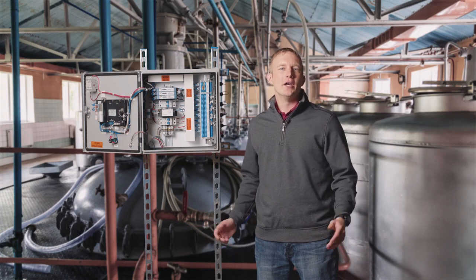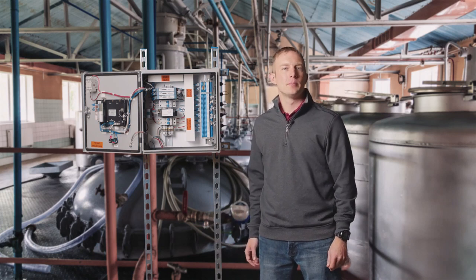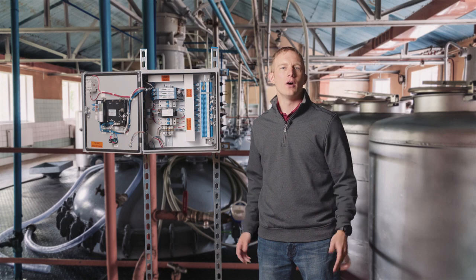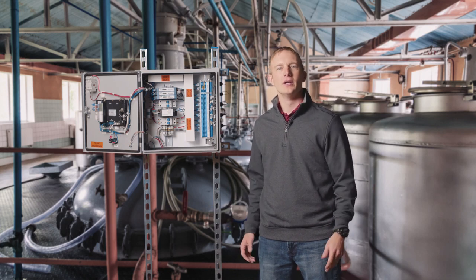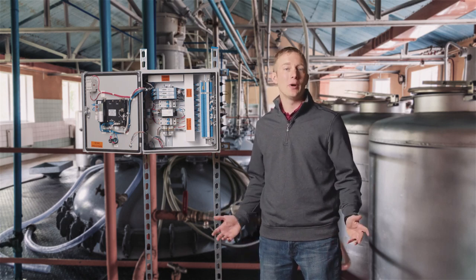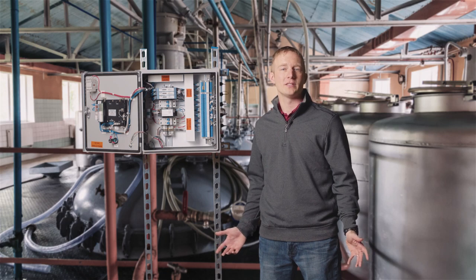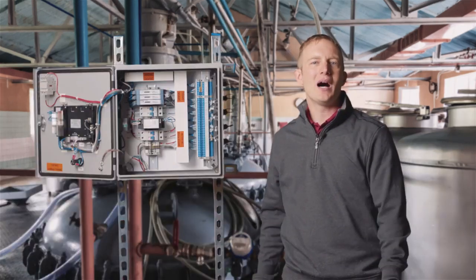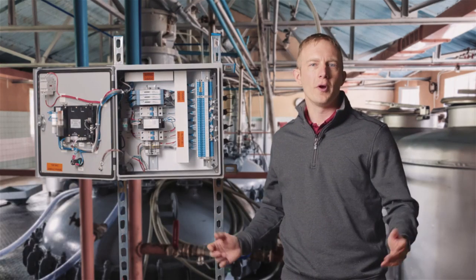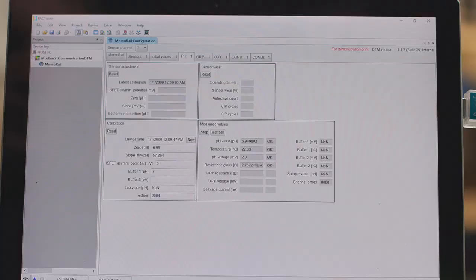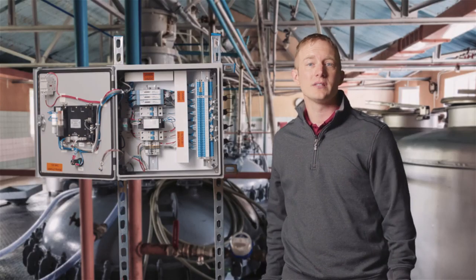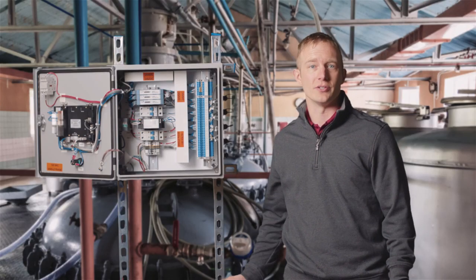Hi, in this video, we'll be walking you through the steps to perform a 2-point calibration on our MemoSense pH sensor utilizing the compact DIN-rail mounted MemoRail Modbus transmitter by Connect. Using Modbus RTU protocol with our MemoRail Modbus transmitter not only allows us to pull the measured values and MemoSense diagnostics data, but it also allows us to write data to our sensor.